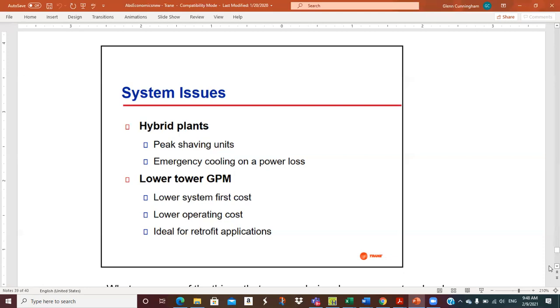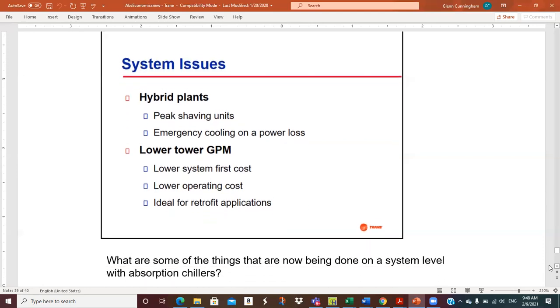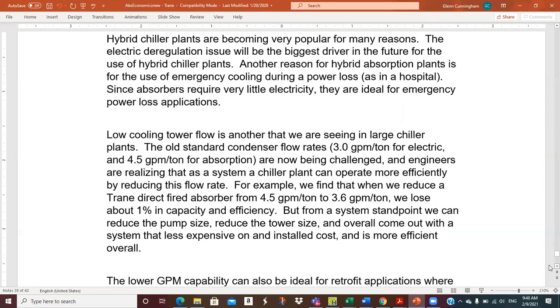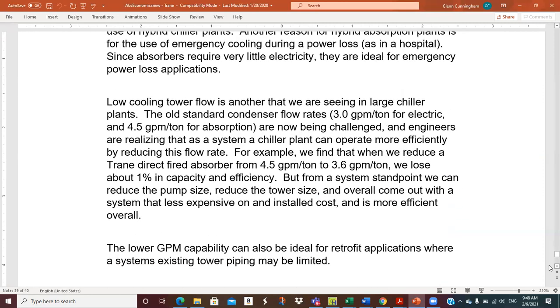Okay, and then I'm going to just review these notes down there. This lower tower GPM, there are some good numbers down here I want you all to look at. Low cooling tower flow is another idea that we're seeing in large chiller plants. So the old standard condenser water ratio, you should know this. This is one of the things that we pound home in the first course. On a centrifugal, when you run the Carrier program and create a cooling tower, it's going to default to 3 GPM per ton, because that's the old golden number for condenser water flows on centrifugal chillers.